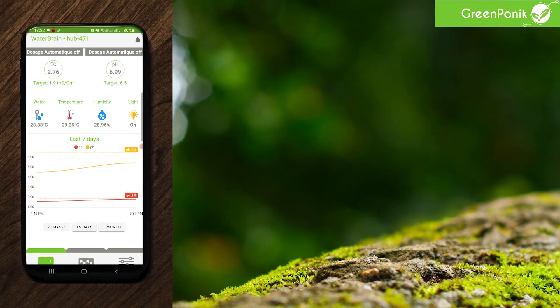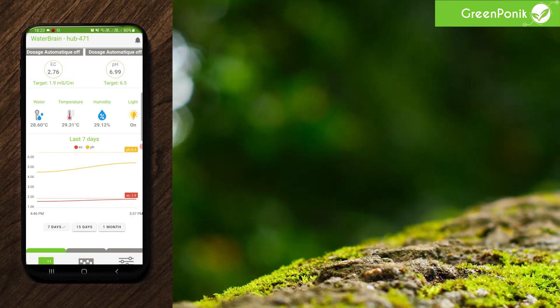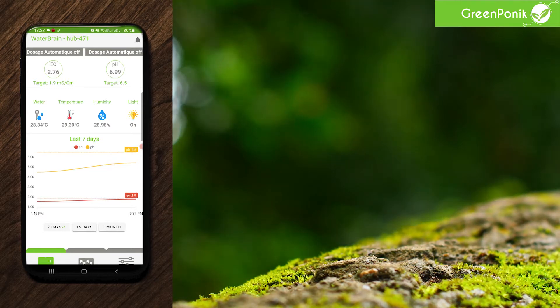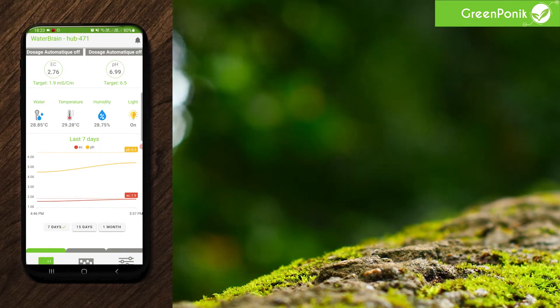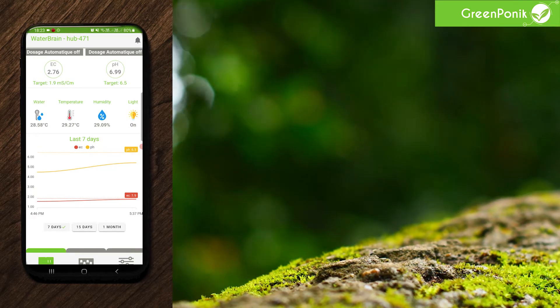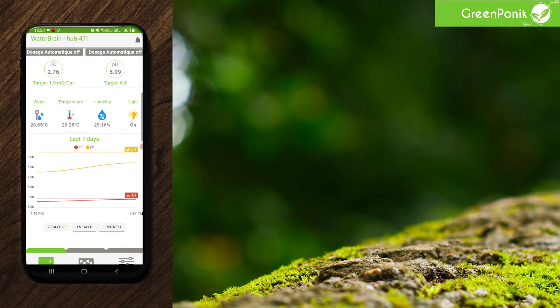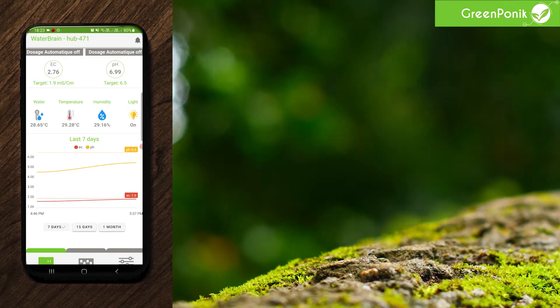At this step, you should have accurate results and you are able to put your sensors back into your water tank after a last cleanup with some plain water. Bear in mind that when you calibrate your sensors, you will maybe not have the exact results you're looking for — the important thing is that you have to be near the result. If we have 6.99 for 7.0, it's okay, it's very near the target. If we have 6.8, it's quite a bit far, and in that case my advice is to send us an email at support@greenponic.com.